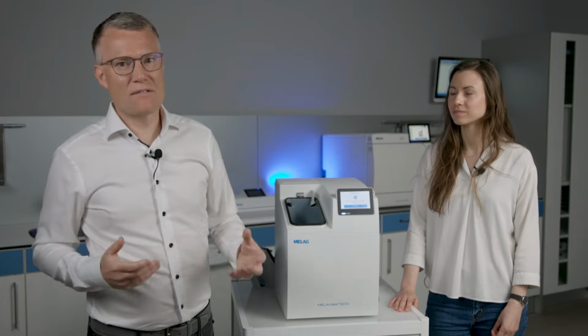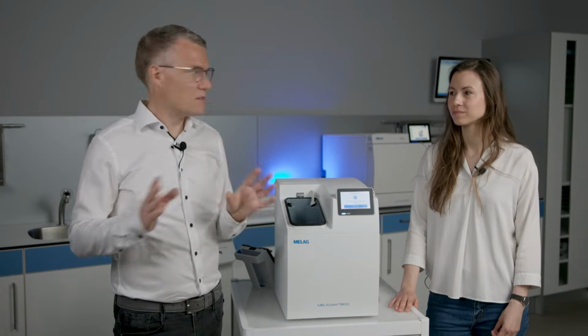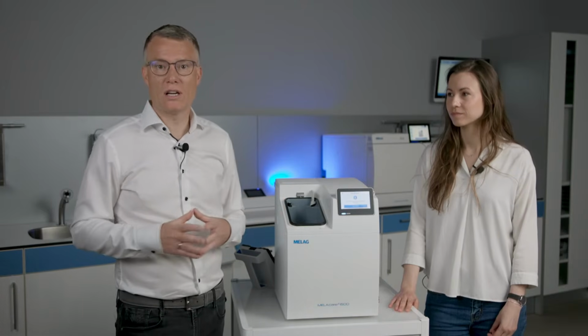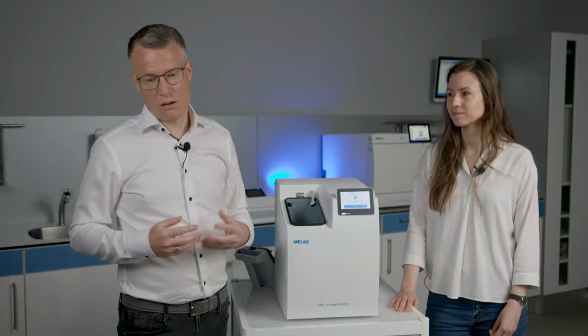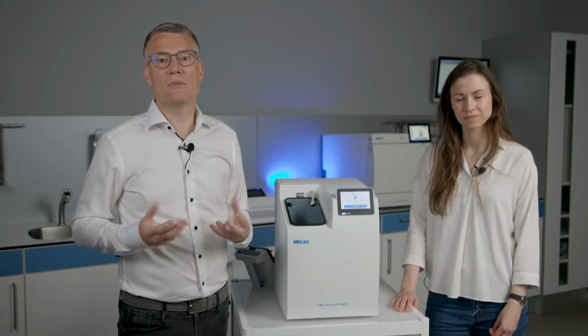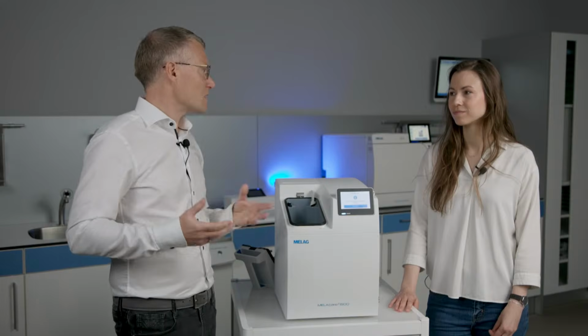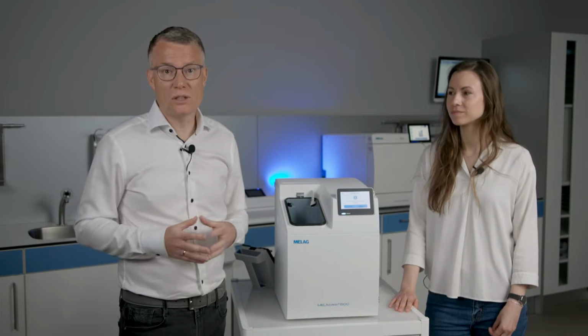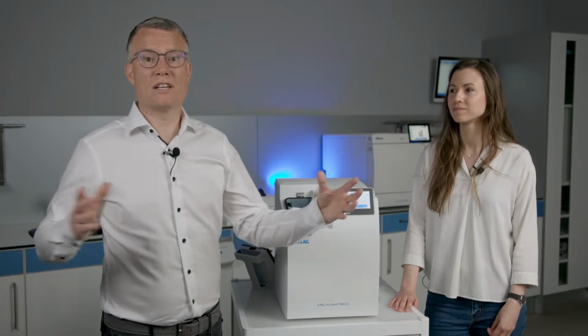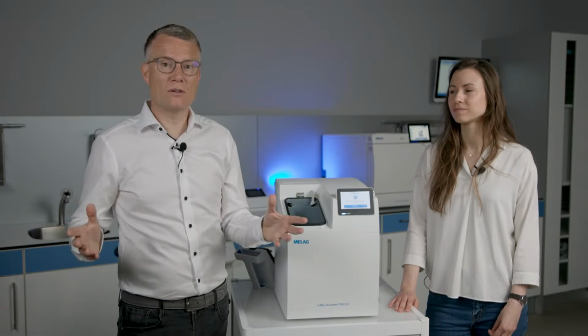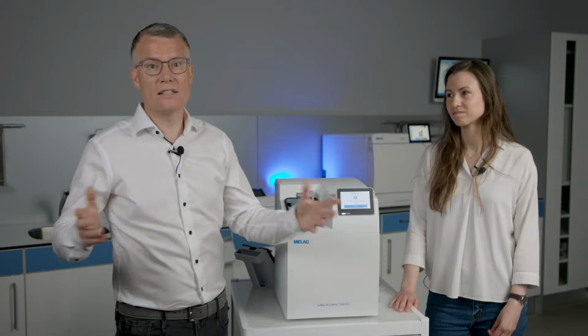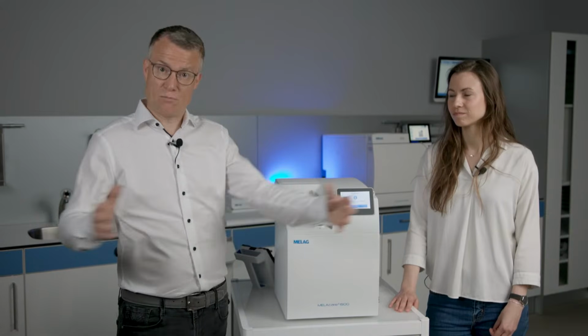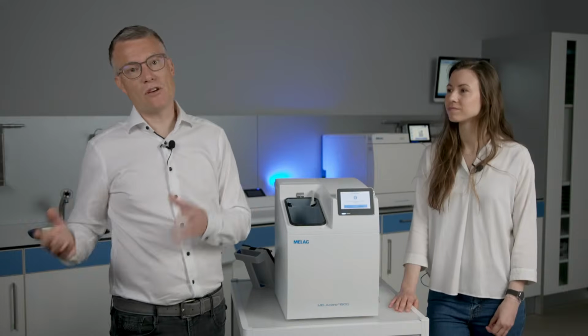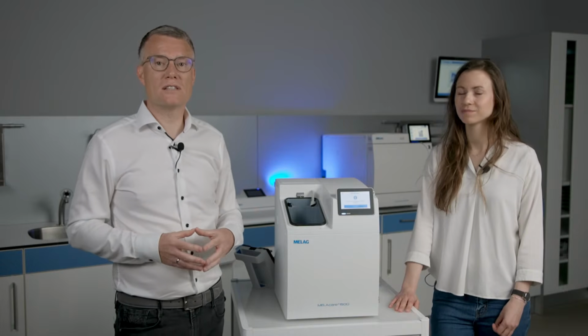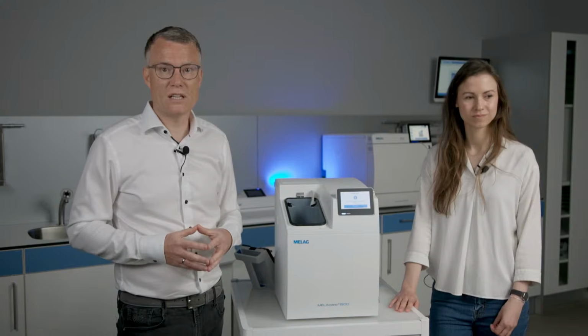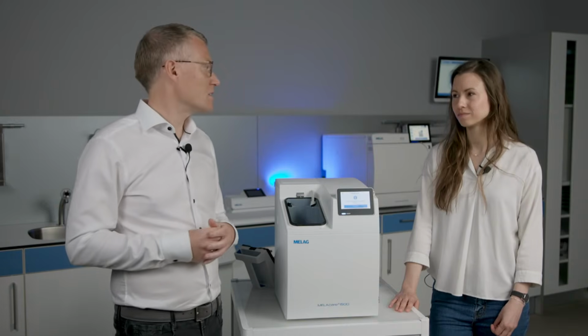Again, you might have space issues, where your sterilization room is a little bit smaller and you are looking for every centimeter that you might be able to save. Then of course a CareClave would be a good idea, because when you have two units, a lubrication unit and an autoclave, you easily need approximately 90 centimeters of space for placing the units. If you have a CareClave, the space that you need is much less. So this is another point to consider as well.